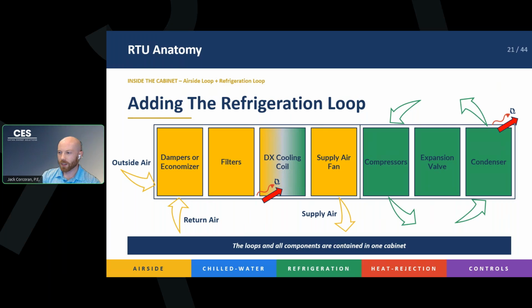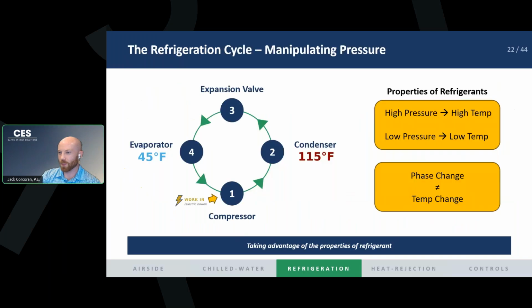So all these sections make up our rooftop unit. With the airside loop, you follow the air through the system, and with the refrigeration loop, you just follow the refrigerant through the system. It's the exact same refrigeration loop we talked about last week in our VRF fundamentals presentation. All we're trying to do is achieve a cold coil where the air flows over it and a hot condenser so we can reject heat down the temperature gradient. Heat naturally flows from hot to cold. We want our hot air to transfer to our cold evaporator, and we want our hot condenser to transfer heat to our hot ambient at 95-degree ambient. A 115-degree condenser is going to do that trick.